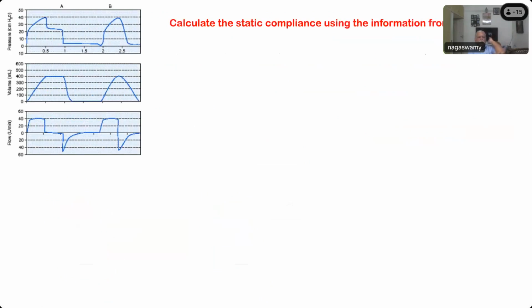Now you are seeing some scalars or graphics of a ventilator. Can you calculate the static compliance using the information from the scalar shown here? Normally you find these three scalars displayed in most of the ventilators. Okay? One is pressure time, second is volume time, third is flow time scalars. So how to calculate the static compliance? How do you interpret this pressure time scalar?